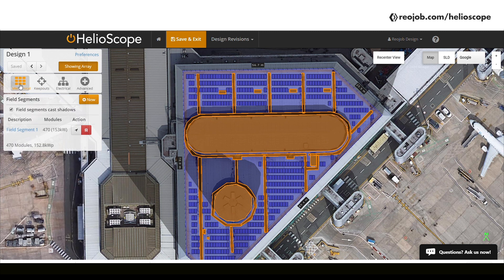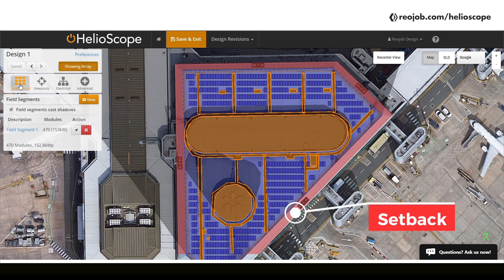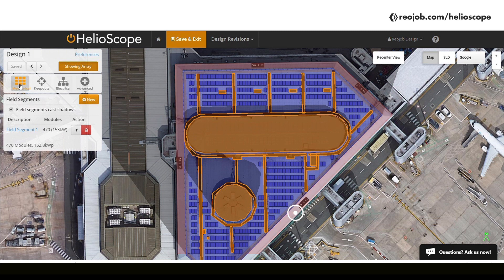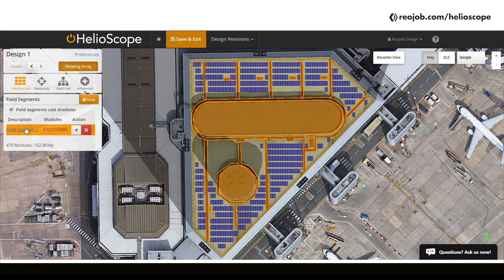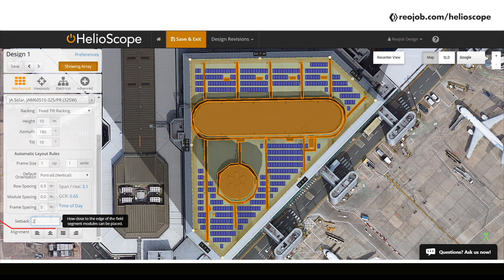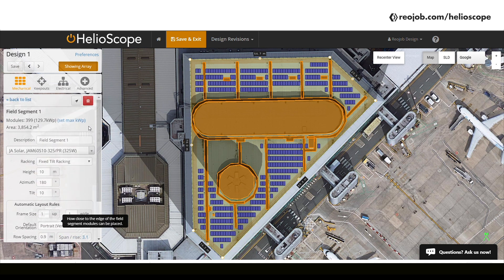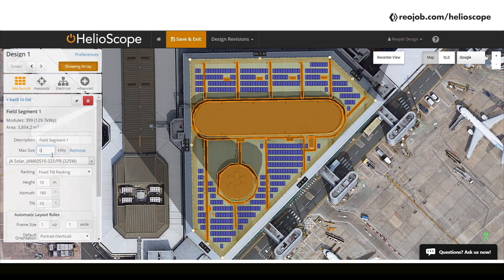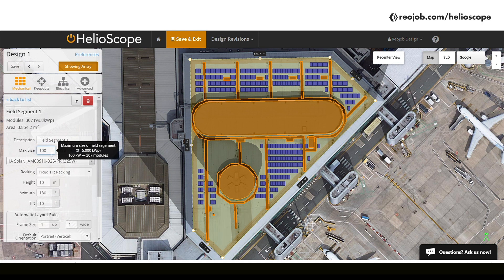If you take a look at the edges of the rooftop, the panels are always a few meters away. This is what is commonly known as a setback. Setbacks are often dependent on local regulations and safety requirements. The closer the panels are to the edge of the roof, the riskier it is as they may fall off. You may add a different setback accordingly, but for this video I'm going to leave the setback at 2 meters. Speaking of local regulations, in some countries you cannot exceed a certain plant size — you can set that upper limit right here, which will ensure that the design does not exceed it.